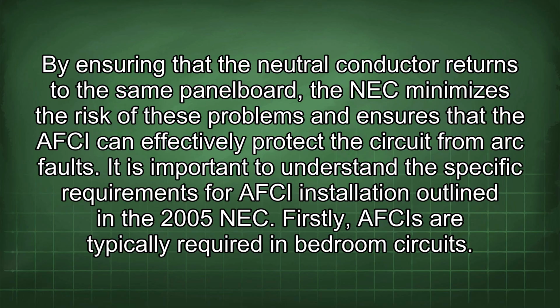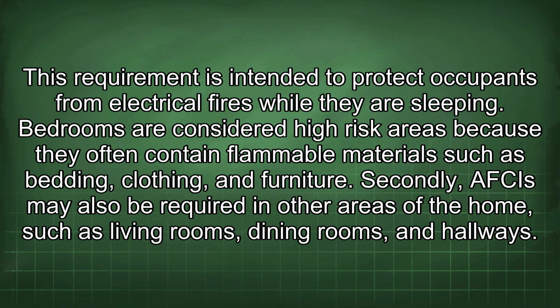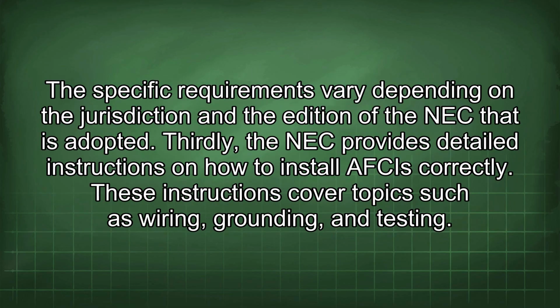It is important to understand the specific requirements for AFCI installation outlined in the 2005 NEC. Firstly, AFCIs are typically required in bedroom circuits. This requirement is intended to protect occupants from electrical fires while they are sleeping. Bedrooms are considered high-risk areas because they often contain flammable materials such as bedding, clothing, and furniture. Secondly, AFCIs may also be required in other areas of the home, such as living rooms, dining rooms, and hallways. The specific requirements vary depending on the jurisdiction and the edition of the NEC that is adopted.